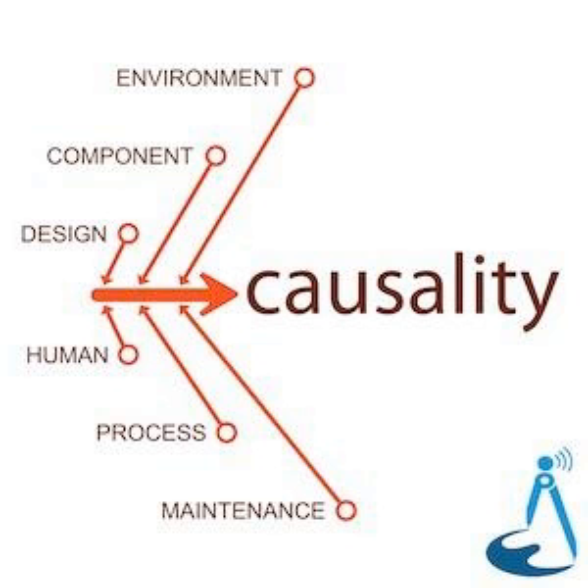The impact of the tsunami had already destroyed the seawater lift pumps on the ocean side of the seawall, because they had been mounted lower and closer to sea level. And there are additional power systems to circulate cooling water. In this case, there's an emergency backup battery, a UPS system, that was able to power cooling pumps for 8 hours by design. Unfortunately, the flooding from the tsunami destroyed the batteries in Units 1 and 2 because they also were in a low-lying area of the plant. The slightly newer Unit 3 batteries, however, were not damaged and surprisingly lasted as long as 30 hours before they were depleted, which far exceeded their original 8-hour design life.